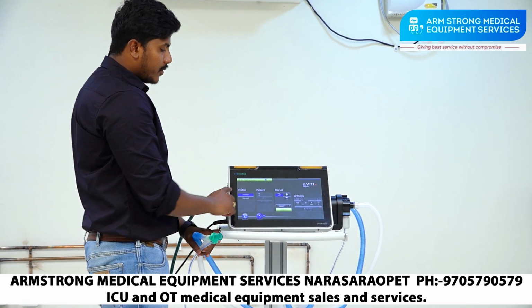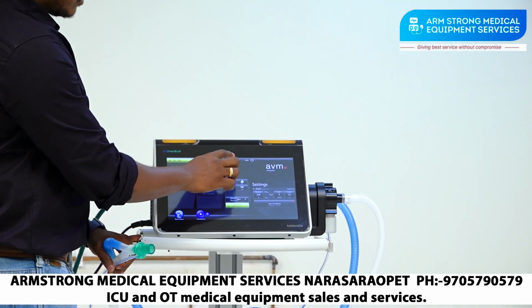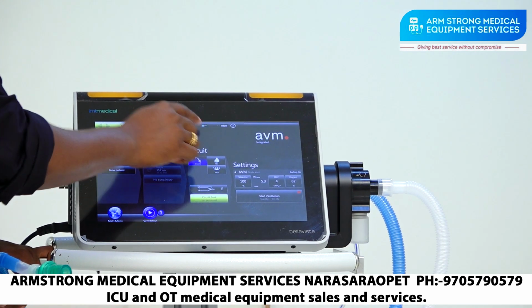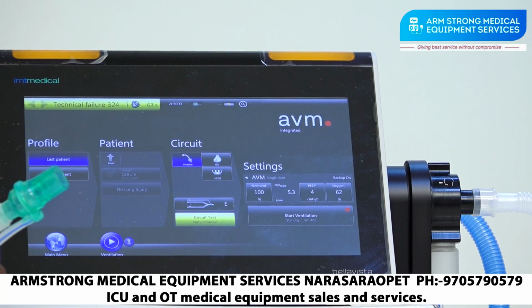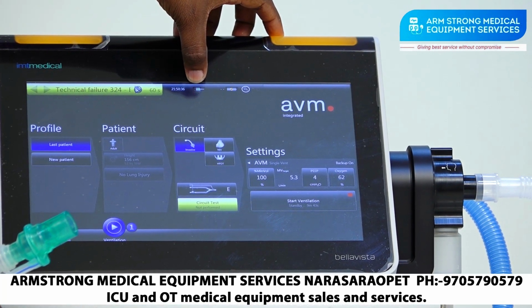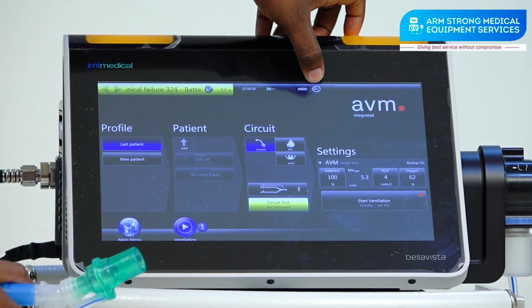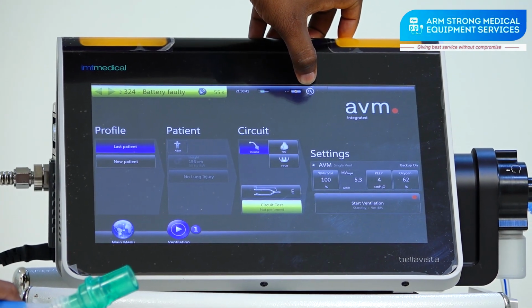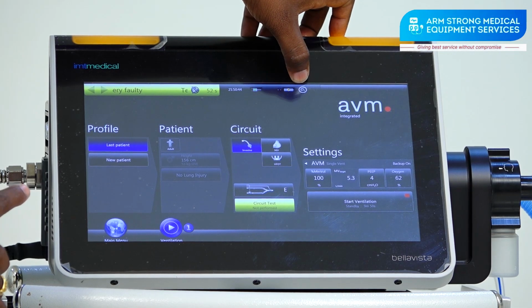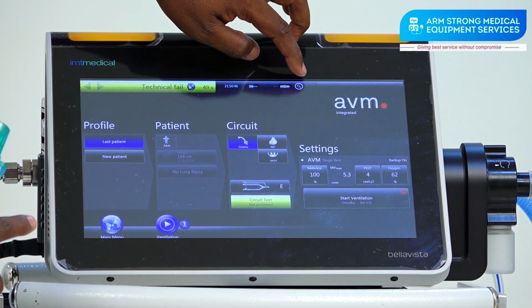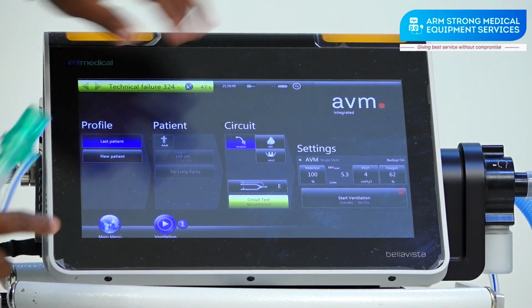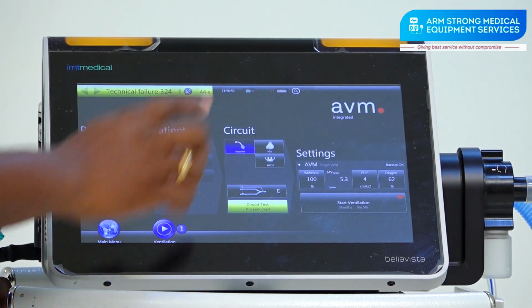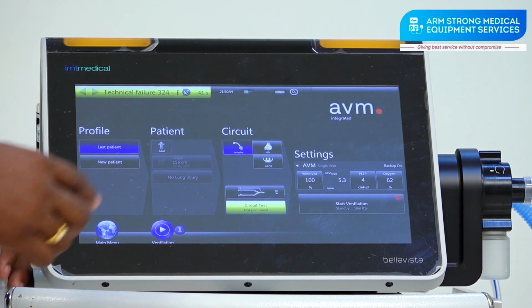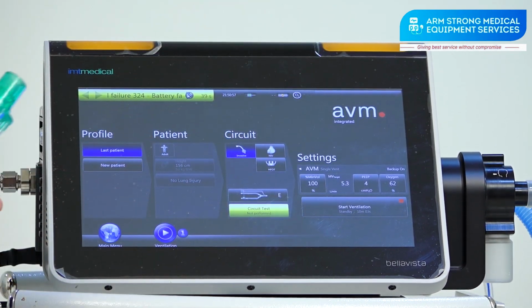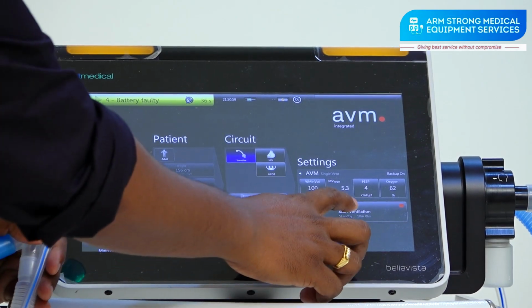See, and one more thing, after all these selections, you have to see this also here. Here you see the mains AC power indication, and here you can also see whether the mains power is connected or not, and here O2. If the O2 central mains connection is not connected, it will show a wrong symbol. Now it is connected, so it is okay. So we have to see this also along with the AC power indication to ventilate the patient without interruption. Now I am checking this ventilator with the test line.